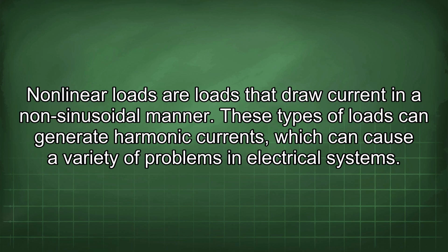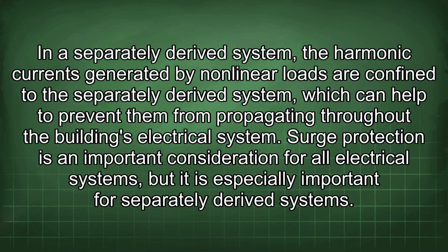Nonlinear loads are loads that draw current in a non-sinusoidal manner. These types of loads can generate harmonic currents, which can cause a variety of problems in electrical systems. In a separately derived system, the harmonic currents generated by nonlinear loads are confined to the separately derived system, which can help to prevent them from propagating throughout the building's electrical system.